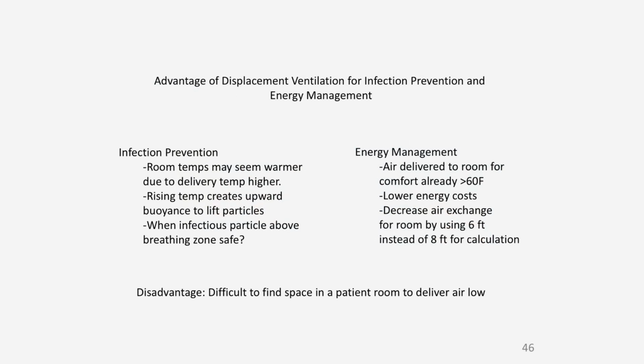So slide 46. Infection prevention. Rooms may seem warmer due to delivery of temperatures at a higher level. Rising temperature creates an upward buoyancy. When infectious particles are above the breathing zone, it's more than likely safe. Energy management, again, you get warmer air delivered. It lowers energy costs, and it decreases the air exchange for rooms by using 6 feet instead of 8 feet for calculation, which, again, is about an average height. So we do get some advantages there. Disadvantage, it's difficult to find space in the patient room to deliver the air at a low level. So there are disadvantages, but yet it would be a good thing for infection prevention in our waiting areas in hospitals.